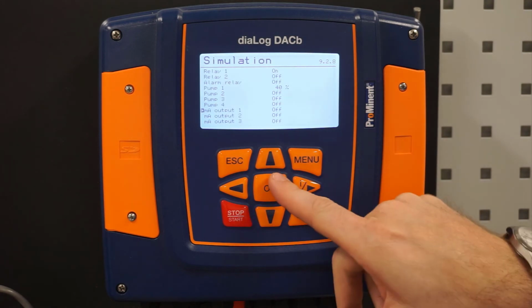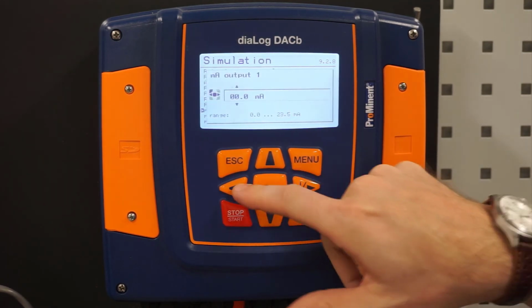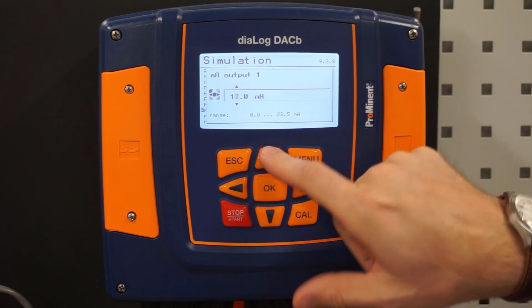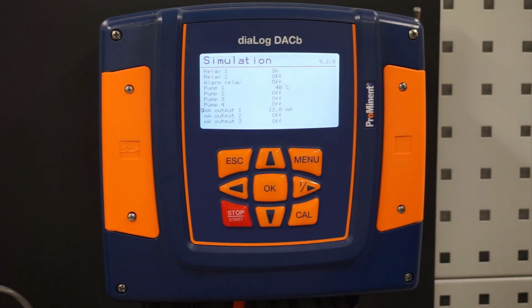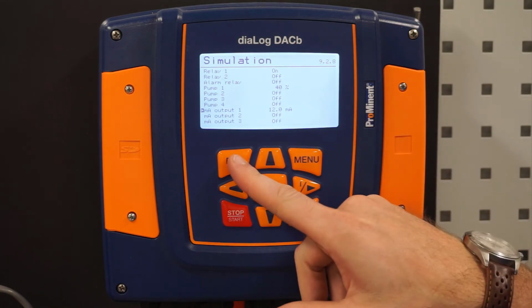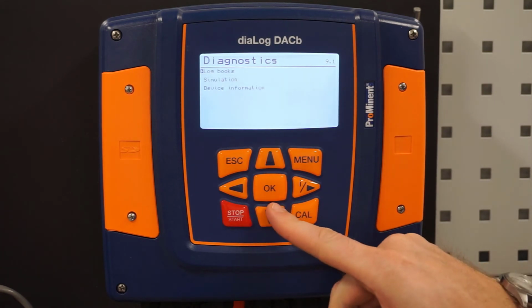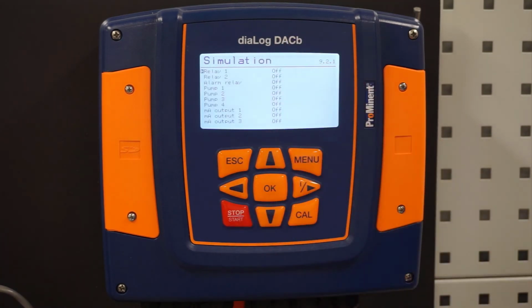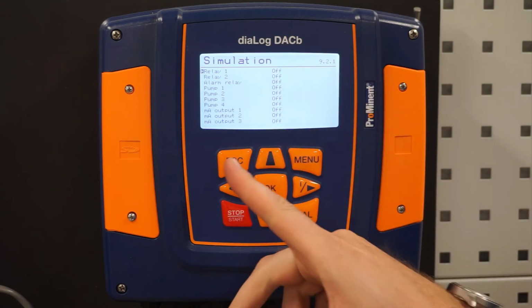Or we can go down, remember we have 3 milliamp outputs, we can go in there and we can simulate a signal and tell the operators that they can expect to see 12 milliamps back at maybe their SCADA or their control room. Nice thing here is if I back out, you'll notice when I go back in, it turns those all off, so I don't have to worry about accidentally backing out of that screen and leaving a pump running at 40% speed. It will turn them off the second I leave the simulation menu.